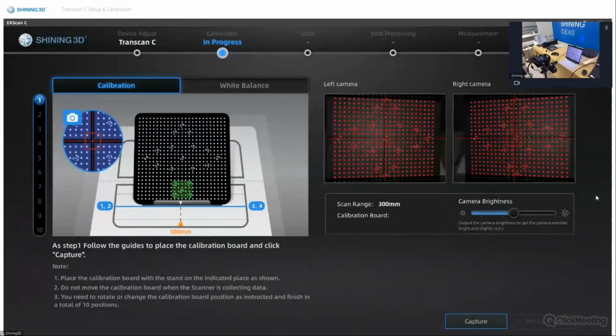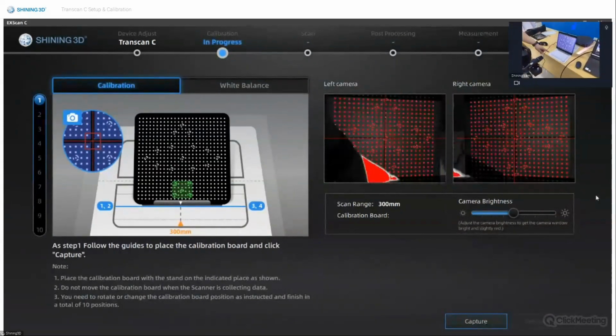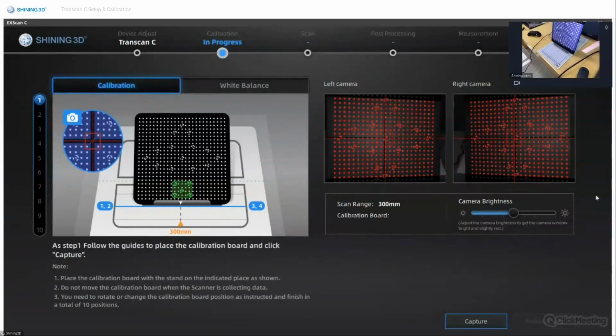Here we are entering the calibration window, and you will be able to see two things on the software interface. On the left, it will be the instruction for the calibration, and on the right, you will be able to see both camera feeds. Okay, so for the calibration, both for 300 and 150, we will go through 10 steps. So you will be taking 10 shots of pictures for the calibration. And you can also see the marks on the calibration pad labeled with numbers. It indicates the positions for all the 10 shots.